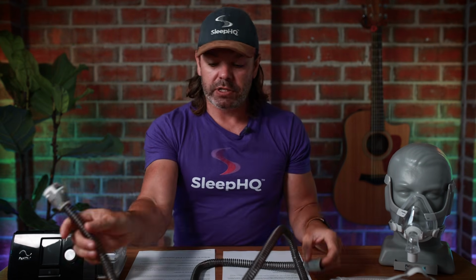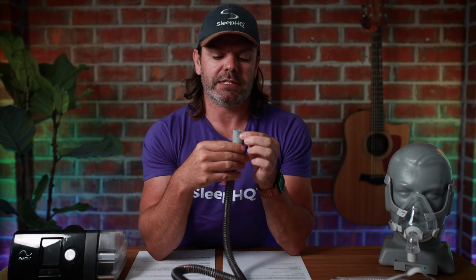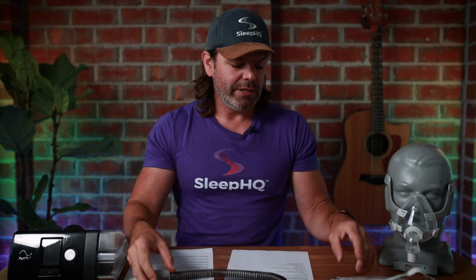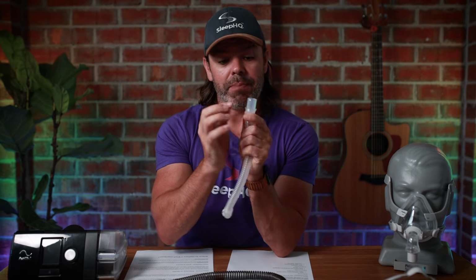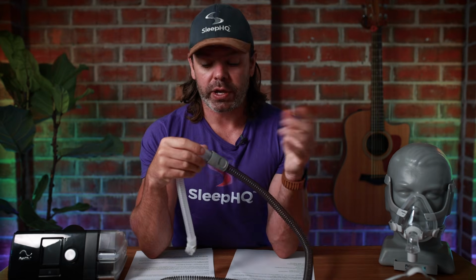They will break eventually. Another thing, these cuffs sometimes start to get a bit loose and they come off the tube. If that starts to happen and your CPAP tube is fine, the rest of the tube is fine, the cuff's getting a little bit loose, just once again, use your brain, guys. You can just wrap a little bit of tape and make that a little bit thicker so that when it plugs in, it's a secure connection.